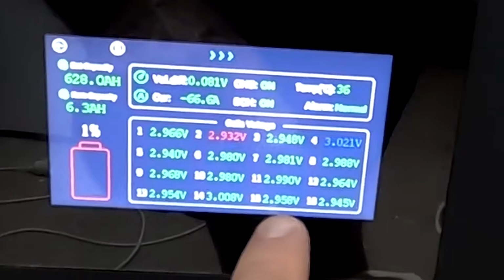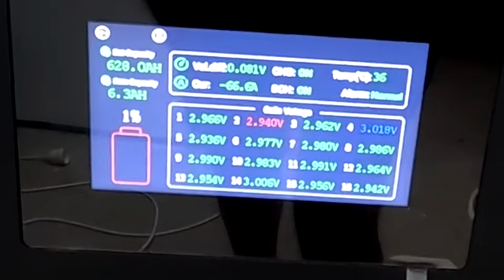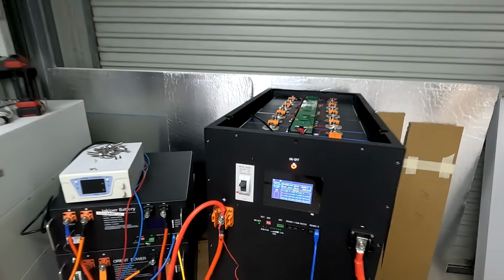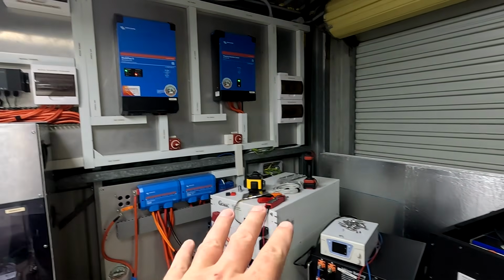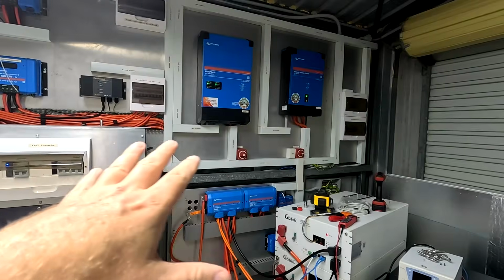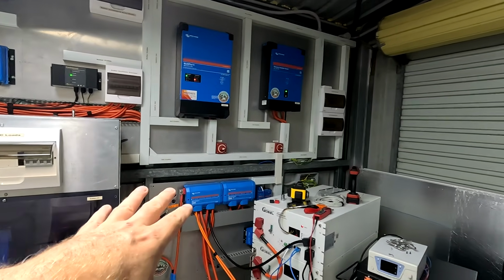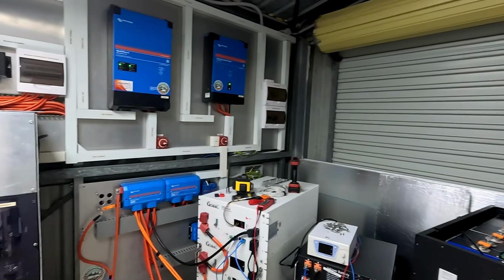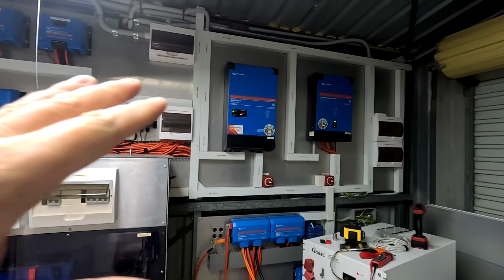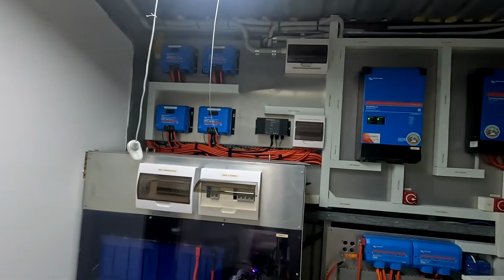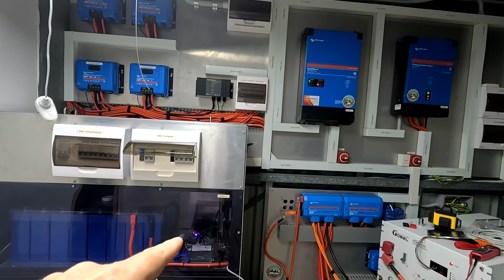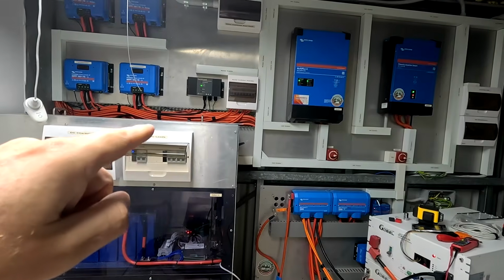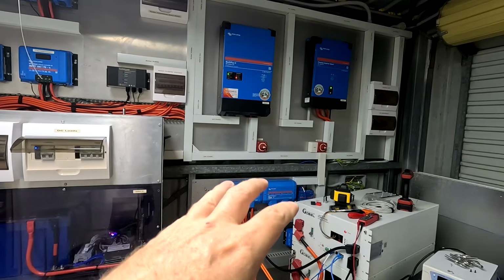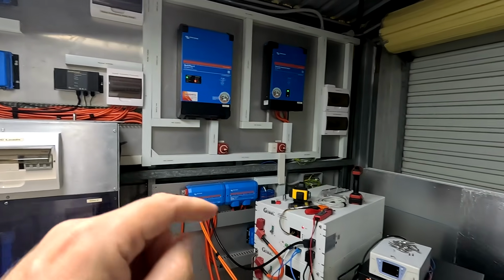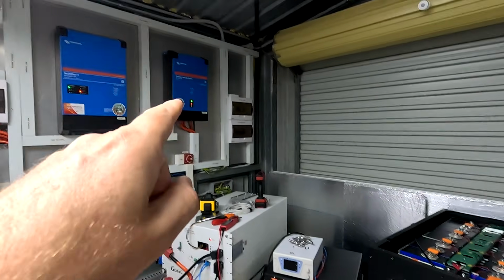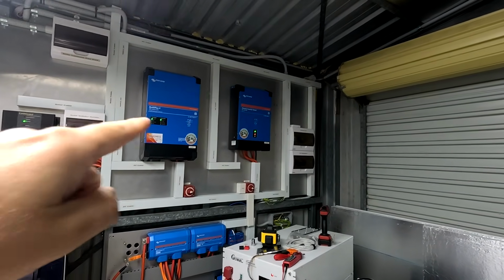Batteries are at 2.9 volts, so we are dipping under 48 volt pack voltage now. What I want to do, very soon, is separate these two systems again, the battery shelf and the Powerwall 2.0. At the moment everything is running from this battery here, but I really want to avoid the multiplus turning off, because all the equipment is running from it. So I want to turn on the battery shelf again, at least one battery, and at the same time turn off the circuit breaker which links the battery shelf and the Powerwall 2.0. Then I've got two separate systems again, but the MB56 battery will still power the Phoenix inverter, which feeds AC into the multiplus again.